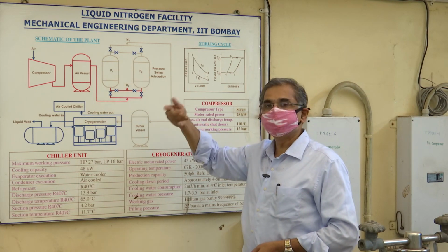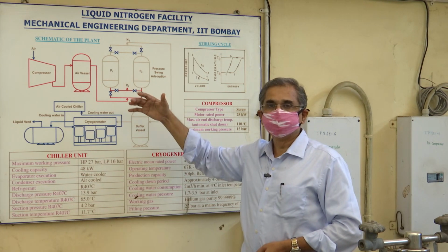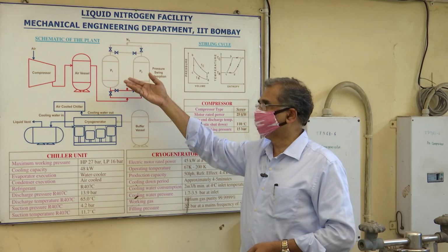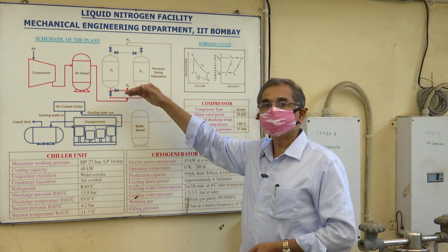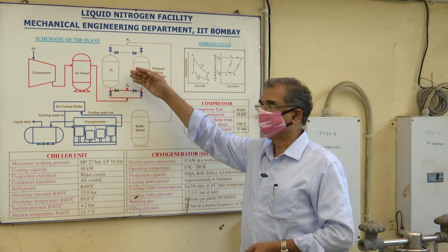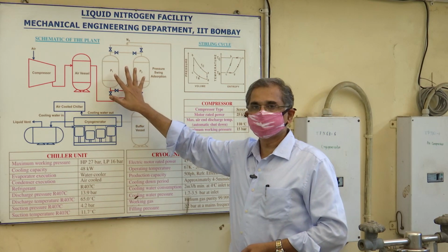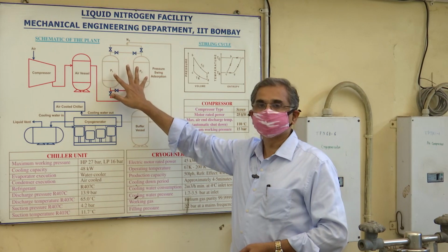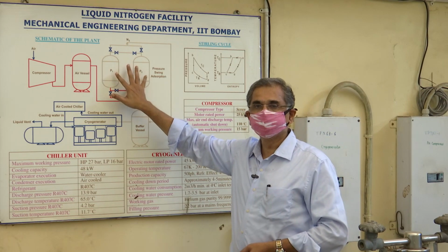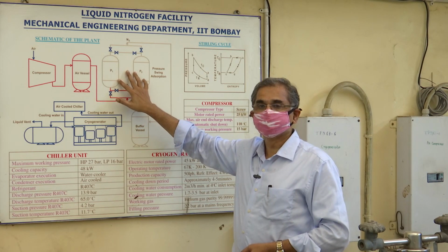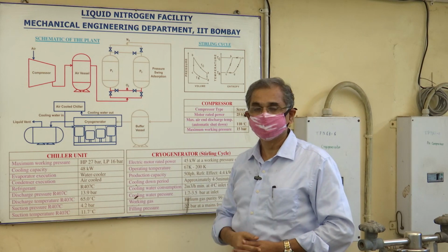This unit we want to change in such a way, it's like a filter unit. The molecular sieves now allow only nitrogen to pass through, but we will change these molecular sieves which will allow only oxygen to pass through instead of nitrogen. So we are going to change only this right now, and in all existing nitrogen plants, if we could change the filter or the molecular sieves of this PSA unit, these nitrogen plants can therefore be converted into oxygen plants, and that is what need of the hour is.